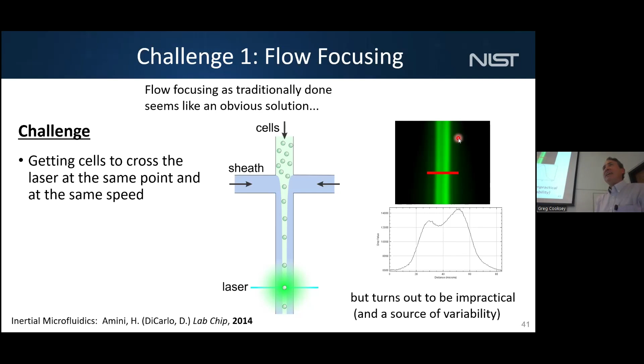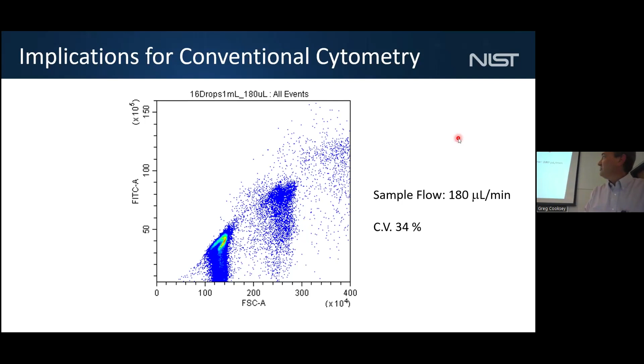Now, this works pretty well for traditional cytometers because your measurement region is quite close to the focusing region. But it's within just a few millimeters that this starts to fall apart. And you can see this in real time in a true flow cytometer if you increase the velocity of the flow. And by increasing the velocity, you're increasing this inertial effect. And so you can see this population fall apart and even sort of fall into these unique two populations.